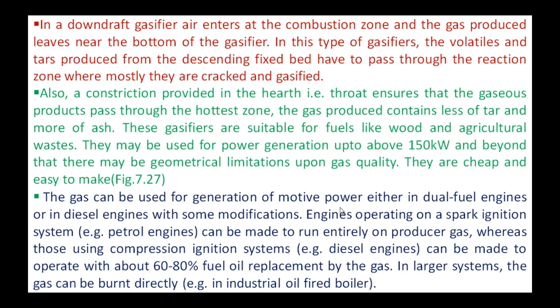The gas can be used for power generation or motive power either in dual fuel engines or in diesel engines with some modifications. Engines operating on a spark ignition system — that is, petrol engines — can be made to run entirely on producer gas. Engines using a compression ignition system, such as diesel engines, can be made to operate with about 60 to 80 percent of fuel oil replaced by the gas, with the remaining 20 to 40 percent being diesel or biodiesel.